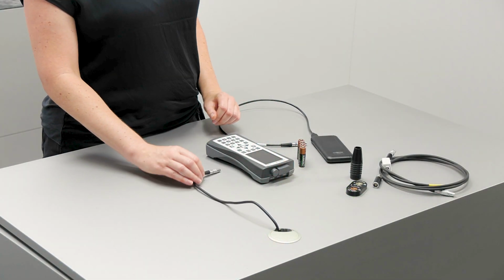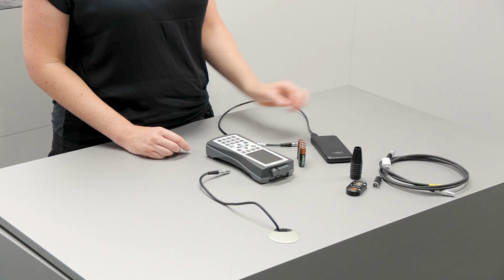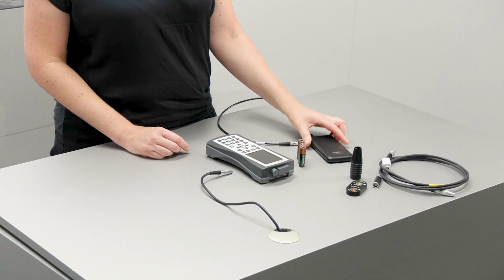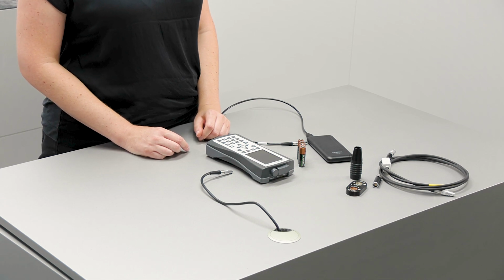The device can be operated either in mains mode with plug-in power supply unit, in rechargeable battery mode with an external rechargeable battery pack, or in battery mode with batteries or rechargeable batteries inserted. The device automatically switches to battery mode as soon as the device is disconnected from the mains or the external rechargeable battery pack is completely discharged. The device features a low-bat display. A built-in buffer storage ensures that the device is not immediately switched off in the event of a loss of supply voltage. Ongoing data recording is completed, and only then is the device shut down. The measurement data is retained.